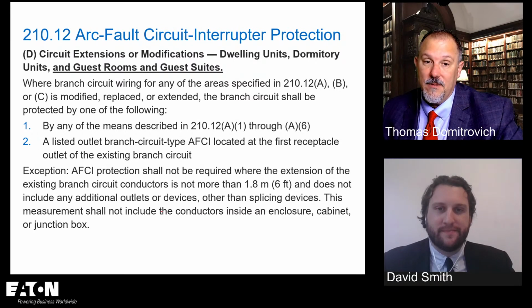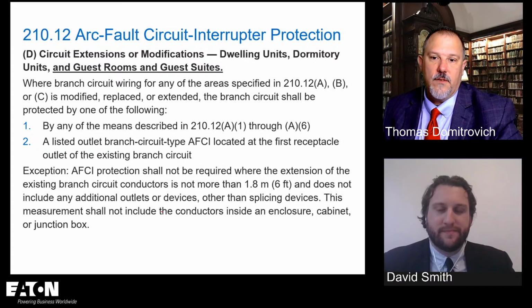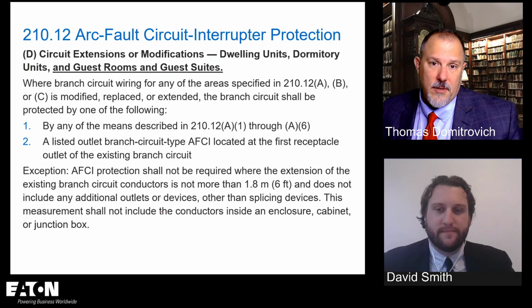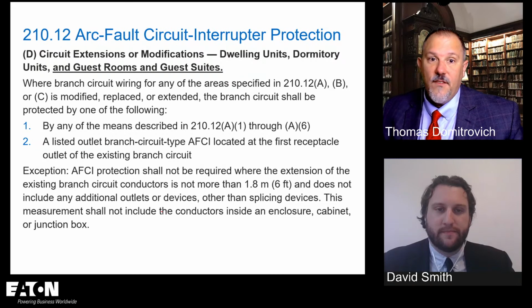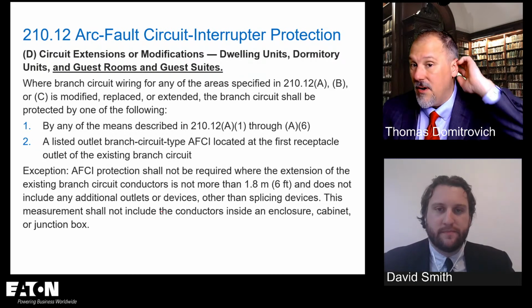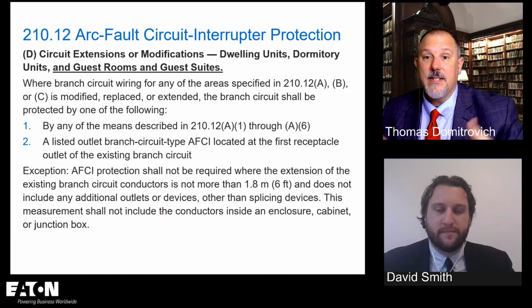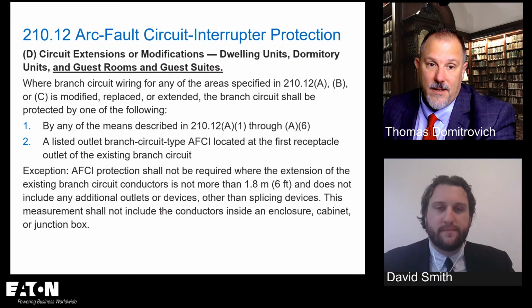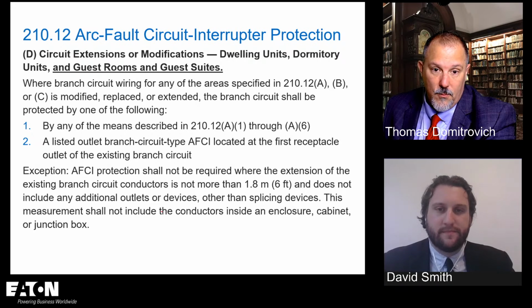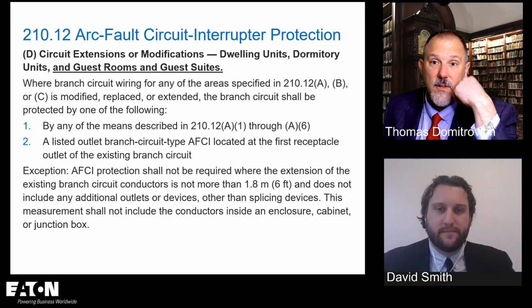So the logic that they used, and I heard that debate, I think we probably could have had better language there, because the only concern was service upgrades. And that's all you had to do is say, look, if you're doing a service upgrade, you don't need to update AFCI protection for the entire home. But if you are modifying, to your point, I'm modifying a branch circuit, I'm pulling things out, I'm changing things around, am I moving not more than 6 foot of conductor?